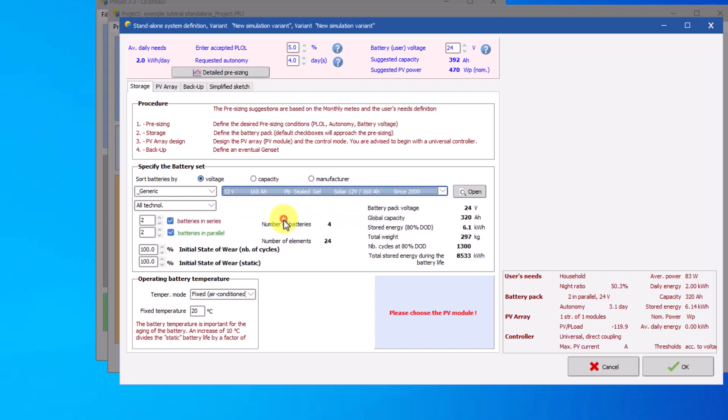The series and parallel configuration will be done automatically according to the pre-sizing help. However, it is not mandatory. By changing the batteries in parallel to 2, the overall capacity decreases to 320 ampere hours, which is lower than the value defined in the sizing tool.